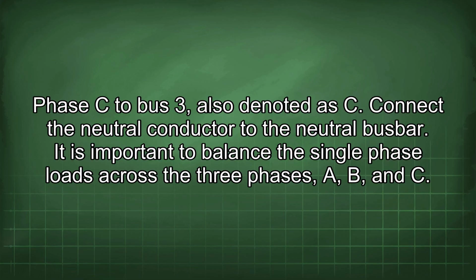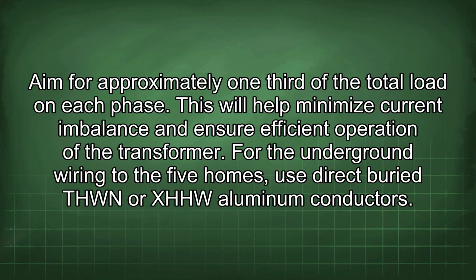It is important to balance the single-phase loads across the 3 phases A, B, and C. Aim for approximately 1/3 of the total load on each phase. This will help minimize current imbalance and ensure efficient operation of the transformer.